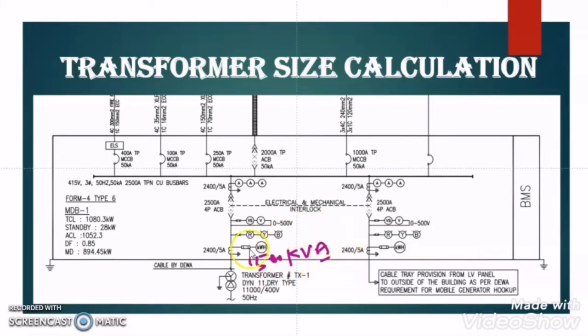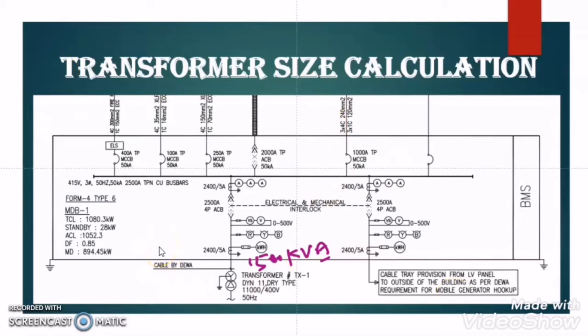But we are not done yet. We calculated the transformer size for this MDB, but we have to do an adequacy check to confirm this transformer fulfills two requirements. First, at the time of starting the largest motor connected with this LV panel, the overloading on the transformer must be under the allowable limit. Second, at the time of starting the largest motor, the voltage dip created must also be under the allowable limit. If our calculated transformer rating satisfies both criteria, then the rating is confirmed as correct. Otherwise, we have to go for a higher transformer size.